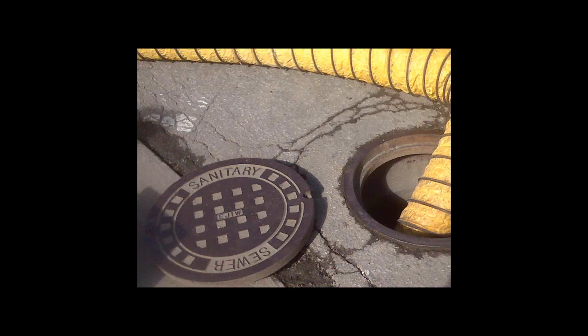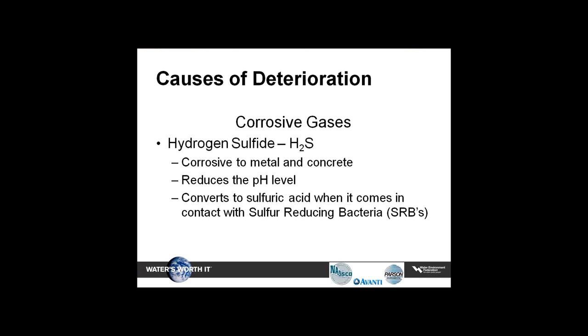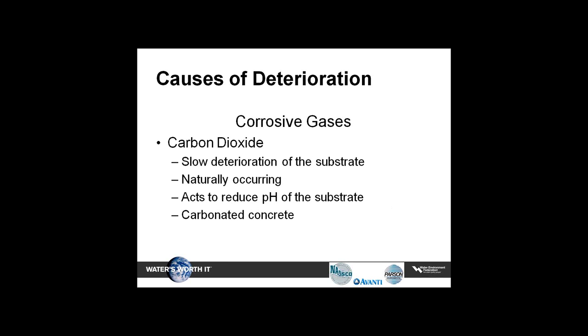Some of the corrosive gases we come across are obviously hydrogen sulfide. It's corrosive to metal and concrete, reduces the pH level, and converts to sulfuric acid when it comes in contact with sulfur-reducing bacteria. Another gas is carbon dioxide, which causes slow deterioration of the substrate. It's naturally occurring and acts to reduce the pH of the substrate, leading to carbonated concrete.